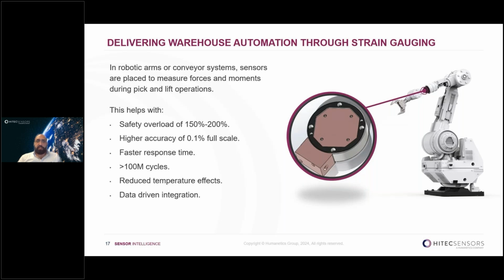This helps with safety overload up to 150% to 200%, higher accuracies of 0.1% of full scale, faster response time, greater than 100 million cycles of fatigue of the load cell, reduced temperature effects, and data-driven integration.